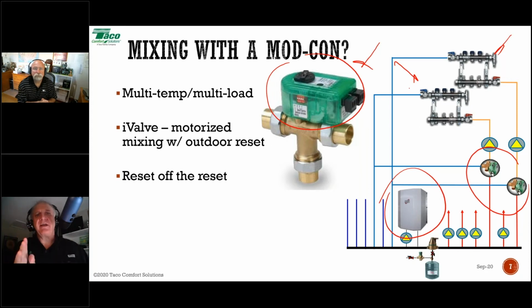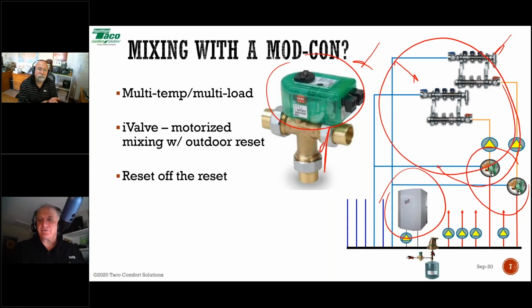So don't be afraid to reset off of the reset, okay? This thing's not going to mess with the boiler reset. This is simply resetting from here on out, okay? It doesn't care what the boiler's doing. It's just taking that water temperature that the boiler's given it and mixing it down to the temperature we need for the radiant, and then it's resetting that. So it's not going to fight with the boiler reset. All it's going to do in this example is send the lowest possible water temperatures back to the boiler.